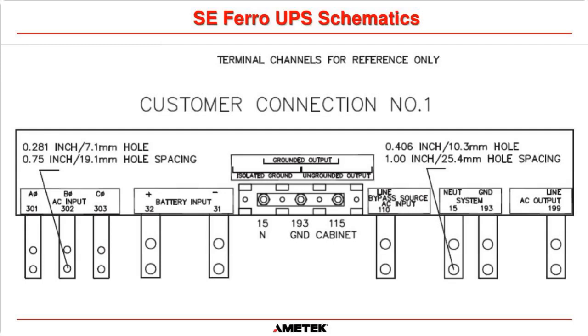Okay, and as you can see, the cables that we mentioned before for the 3-phase input, 301, 302, and 303, that's the cables there. So you would need to connect your cables from your MCC, so A phase, B phase, and C phase, into here. Now, we do give you 2 lugs, so you can use a 2-hole lug if you want to, but it's not necessary. As long as your lug is rated correctly, you can just have 1 lug connected. Okay.